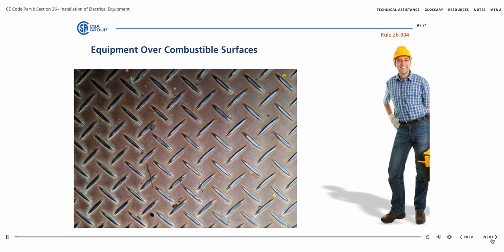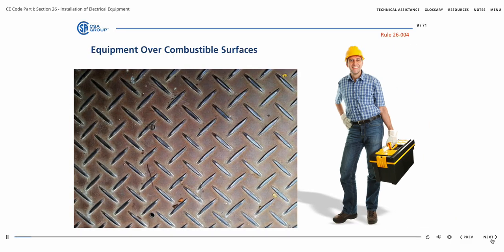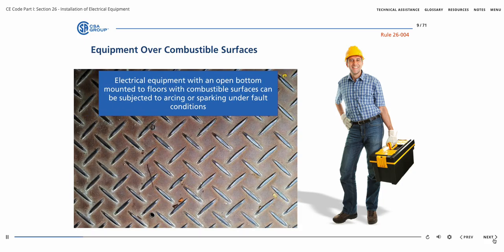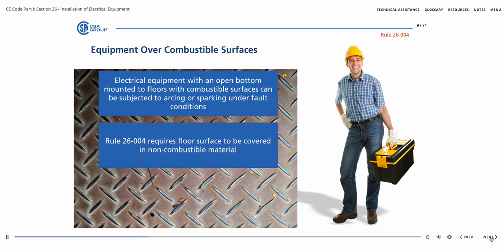It is important to think about safety when installing electrical equipment. Some pieces of electrical equipment are designed to be mounted on a floor. If that equipment has an open bottom and the floor has a combustible surface, then the floor surface can be subject to arcing or sparking under fault conditions through the open bottom. Equipment mounted on a floor is acceptable only if the floor surface is covered with non-combustible material, due to it presenting a hazard if the floor surface is combustible.